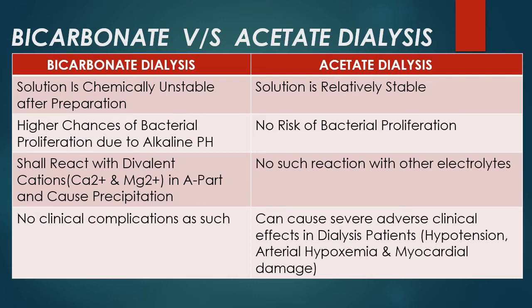Regarding bacterial proliferation: due to the alkaline pH of the bicarbonate dialysis solution, there are higher chances of bacterial proliferation or bacterial multiplication, resulting in contamination. For acetate dialysate concentrate, there is no risk of bacterial proliferation.